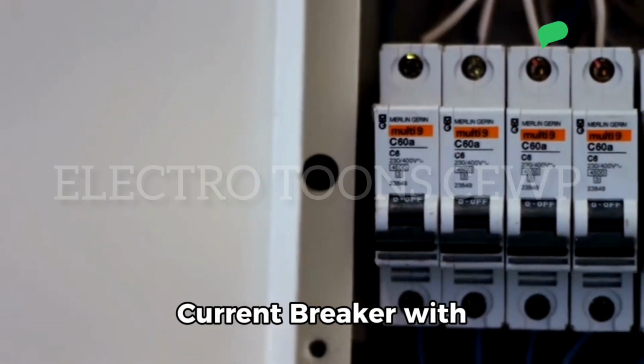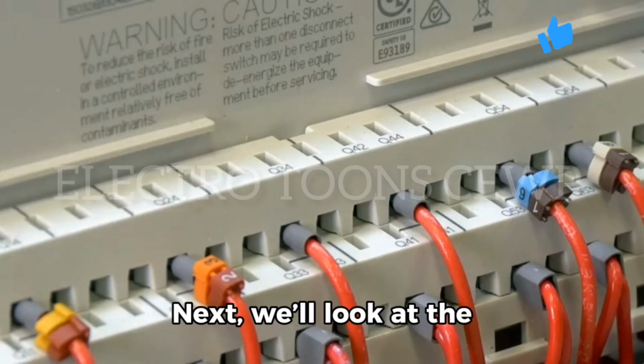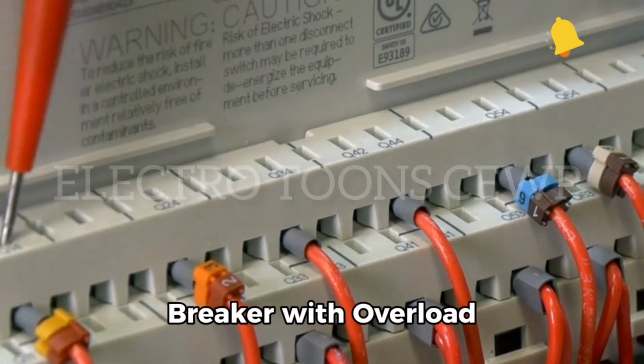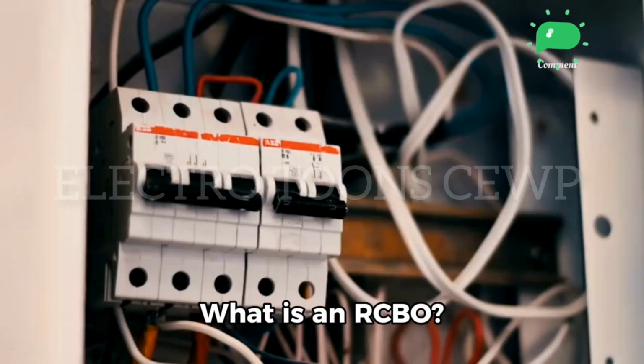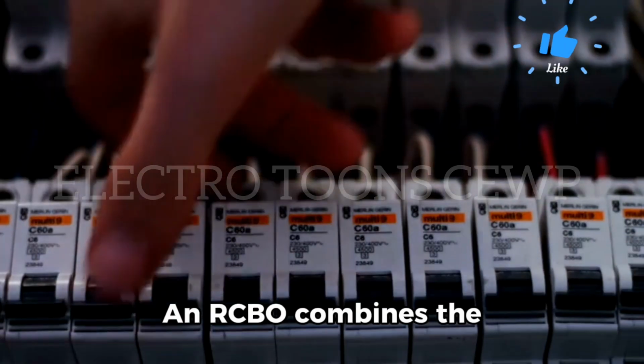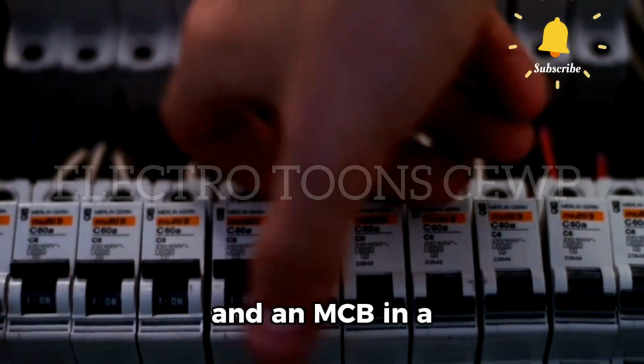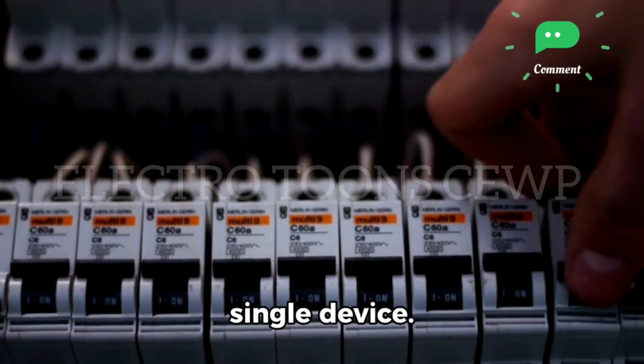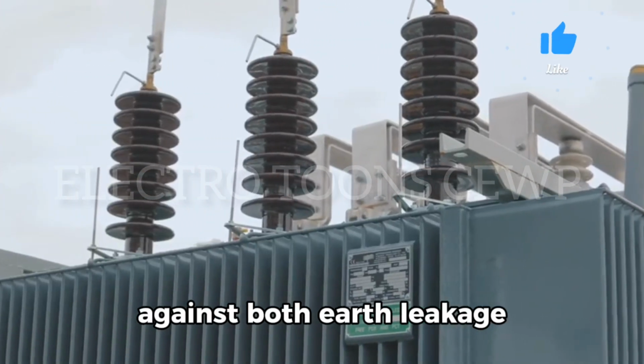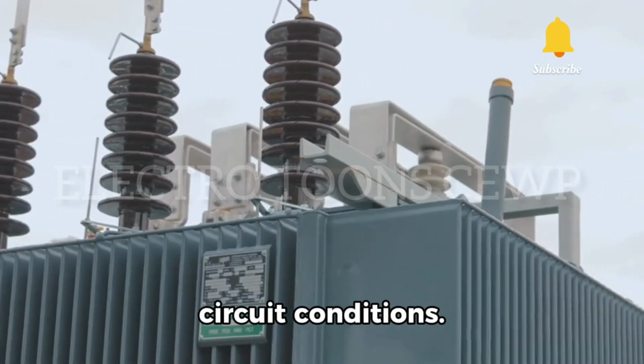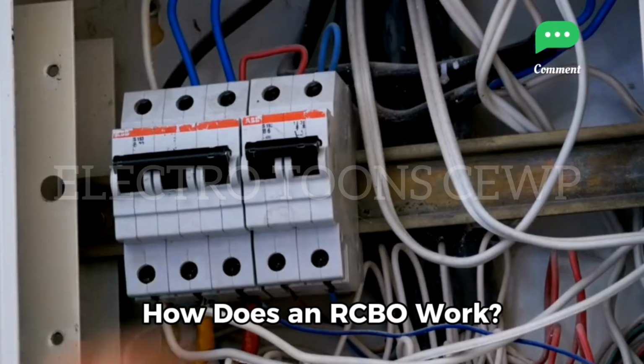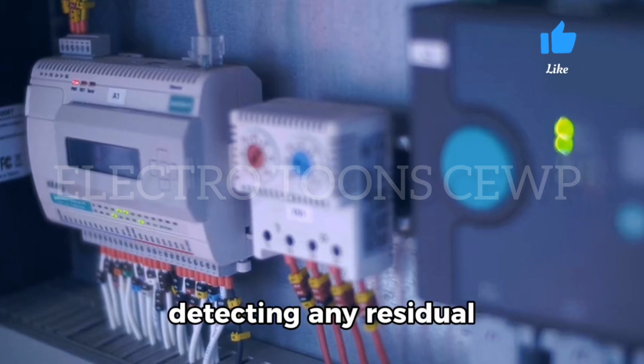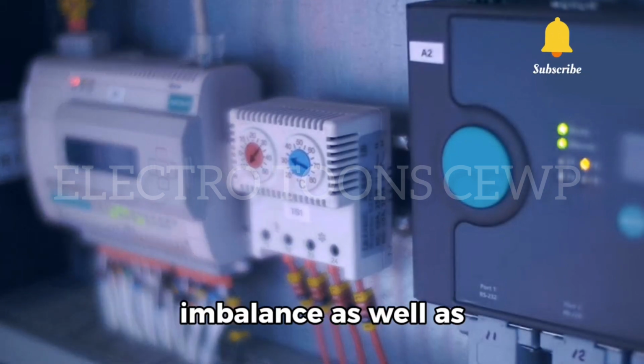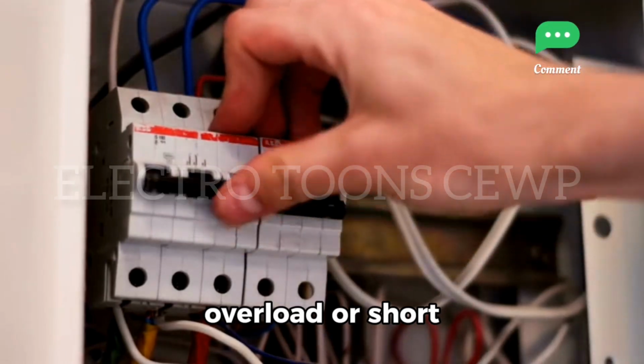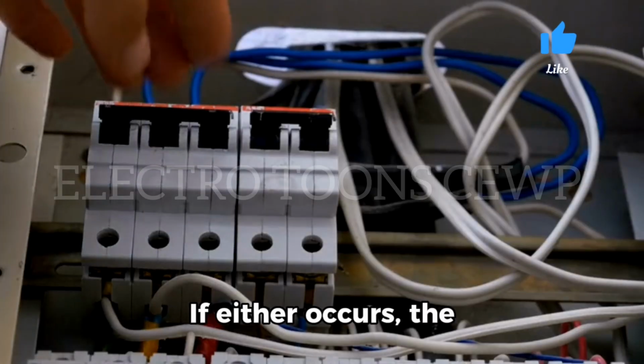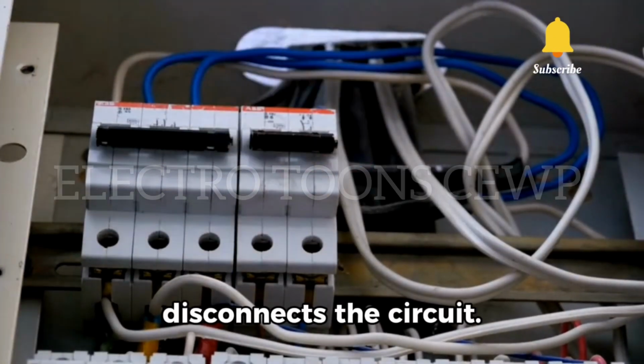RCBO, residual current breaker with overload protection. Next, we'll look at the residual current breaker with overload protection, RCBO. What is an RCBO? An RCBO combines the functions of an RCCB and an MCB in a single device. It provides protection against both earth leakage currents and overload or short circuit conditions. How does an RCBO work? An RCBO works by detecting any residual earth leakage current imbalance as well as overload or short circuit conditions. If either occurs, the RCBO trips and disconnects the circuit.